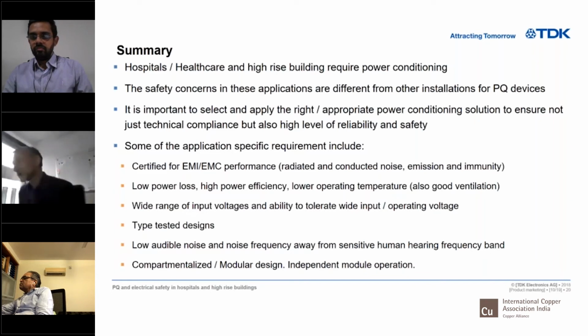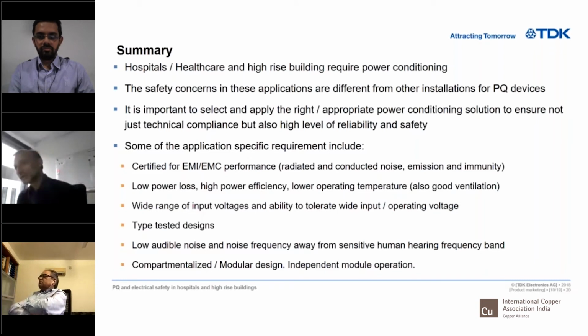You also need to look at long-term reliability and safety. Some specific requirements include certification for EMI/EMC, which is becoming very important as frequencies go up. The equipment should have very low power loss, high efficiency, and lower operating temperature. This isn't just about energy conservation, you do save energy with a high efficiency drive, transformer, or UPS, but you also solve problems related to temperature rise, reliability, and electrical failure. This is more than just tariff-related benefits.